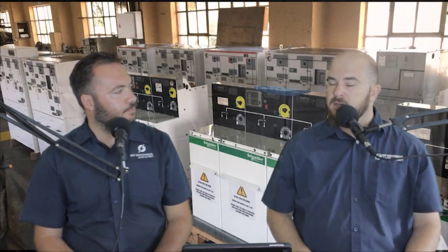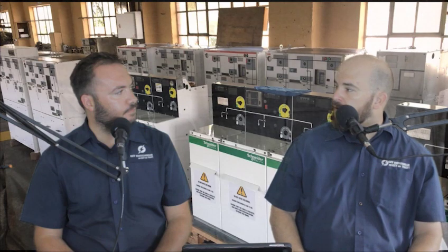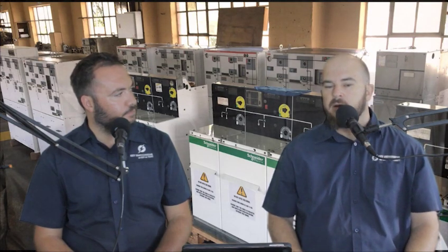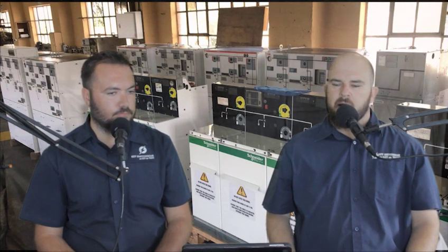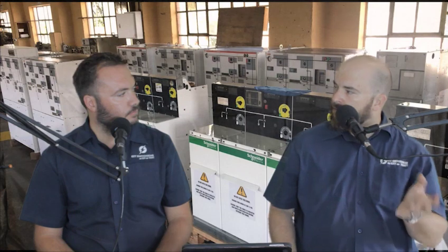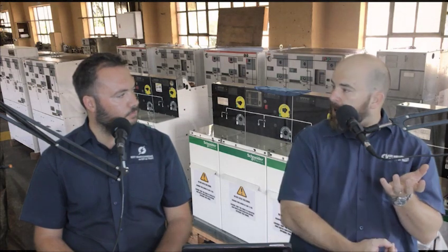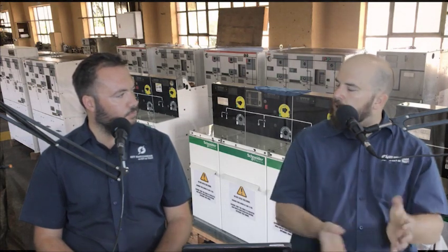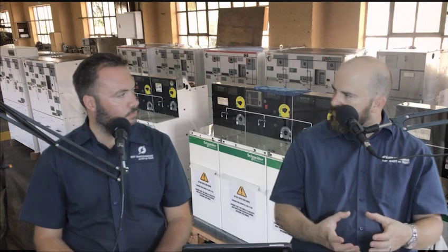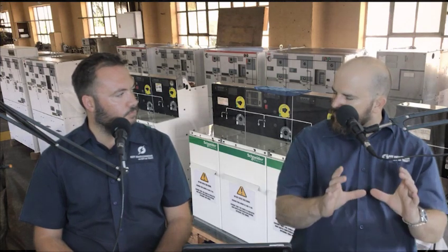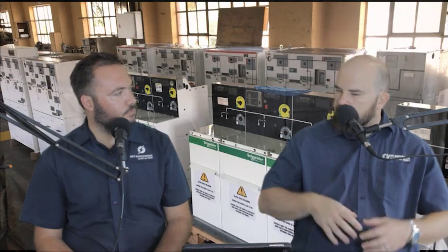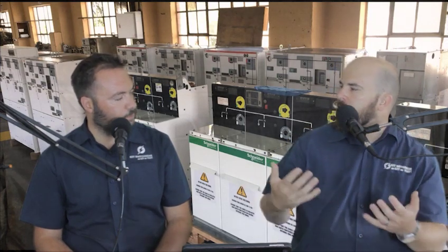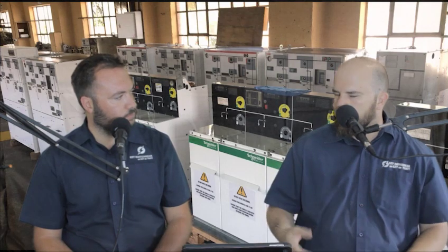Relays are a very big field of their own. We've got a topic that covers quite a lot of relays on our YouTube channel that you can go and look at. In terms of relays, you get basic overcurrent and earth fault relays, which can be self-powered or powered. Self-powered means the CTs generate the power that the relay needs. The moment current flows through that CT, the relay is alive. Other times it's just dormant.